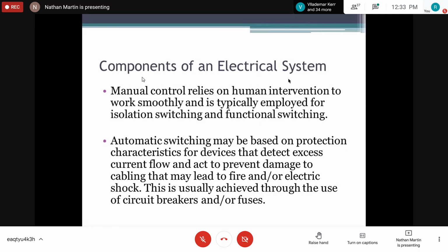All right, so we said the automatic switching. The switching function may be based on protection characteristics, such as your reclosers in your substation, right? These are normally used for protection purposes. If a fault is detected, it will cycle out and then cycle in, right? Depending on its setting, it might be set to cycle twice or 3 times before it's automatically locked out, right? And then they would have to go and manually patrol the line, look for the fault, and then call control and tell them to close the recloser, right? So most of the time it's used for protection purposes. Most systems that have an automatic lockout or switching mechanism are mainly for protection purposes.